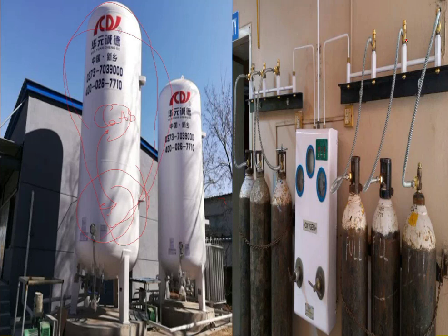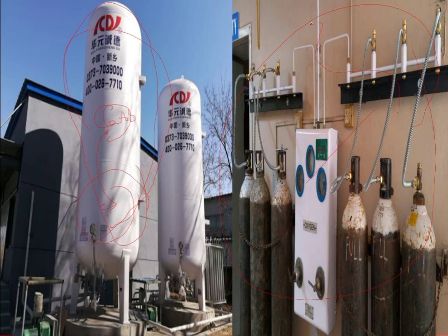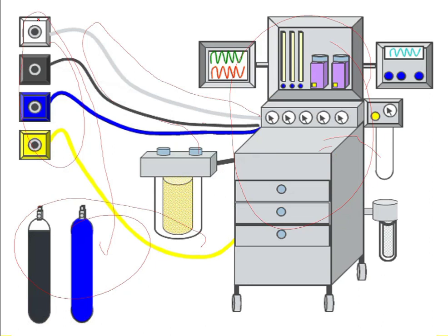As you can see here, we have three cylinders on the right and three cylinders on the left — this is the oxygen manifold. One group of cylinders will supply the pipelines with oxygen. If there is a failure in one group of the manifold, the system will automatically switch to the other cylinders simultaneously. This is how we supply the pipelines.